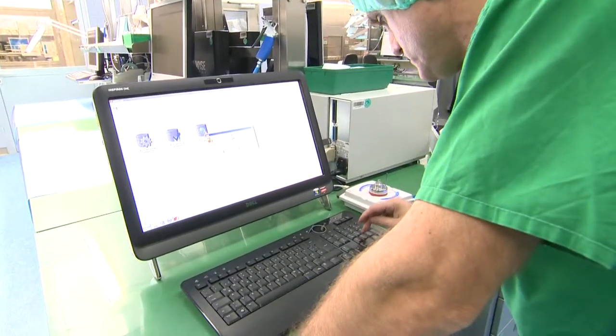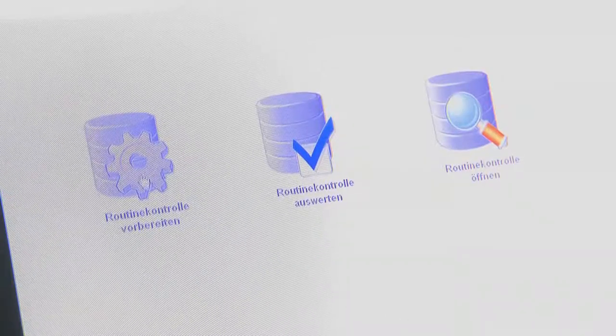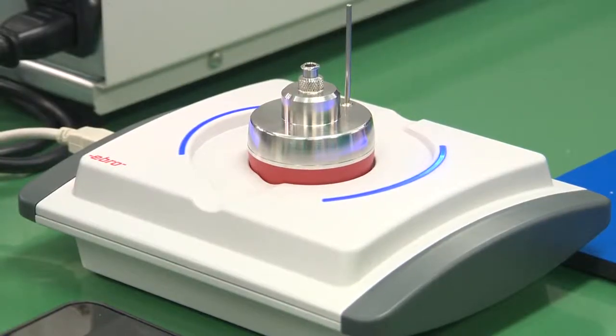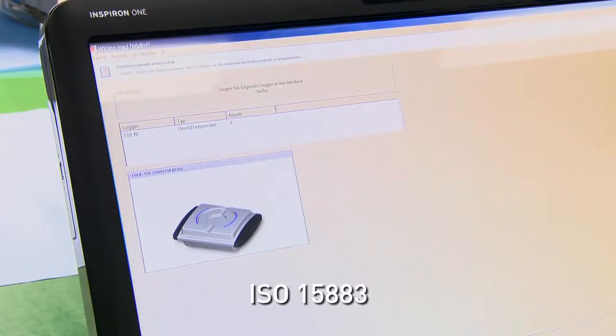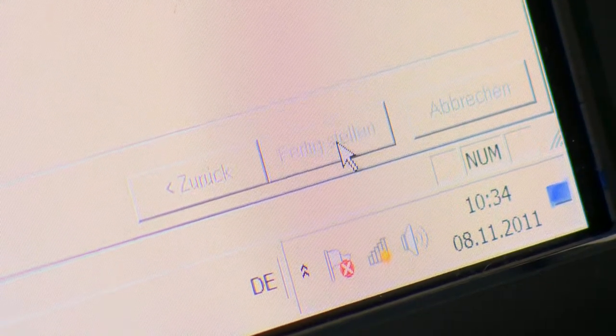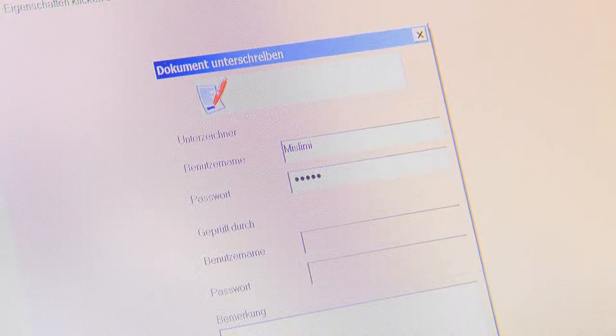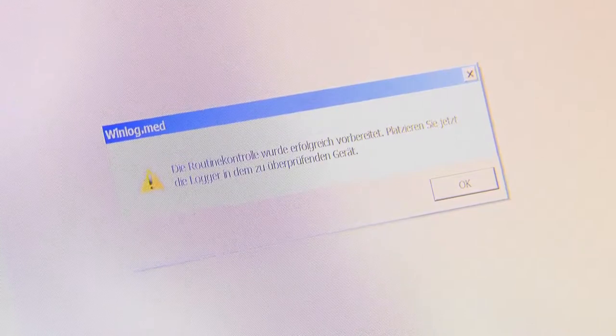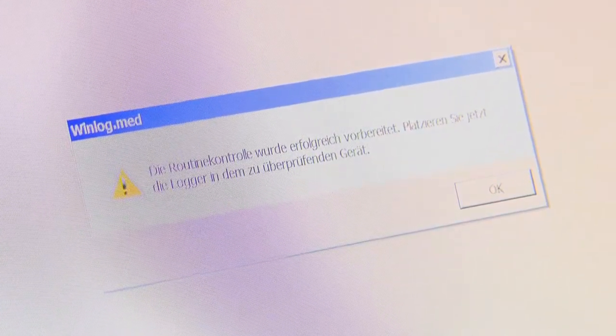An important constituent part of quality assurance is the routine checking of washer disinfector processes by means of data loggers, in accordance with ISO 15883 and the guideline for the routine checking and validation of washer disinfector processes. The procedures include the monitoring of the temperature and pressure of the washer disinfector process and the determination of the disinfection effect by means of A0 value determination.